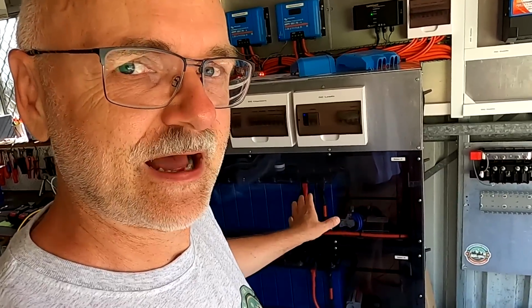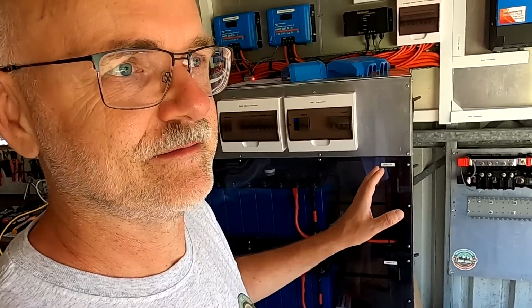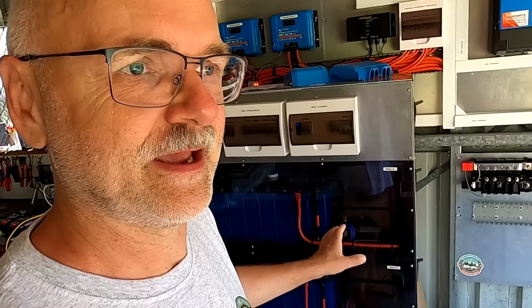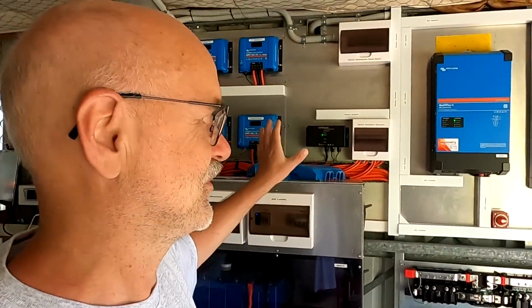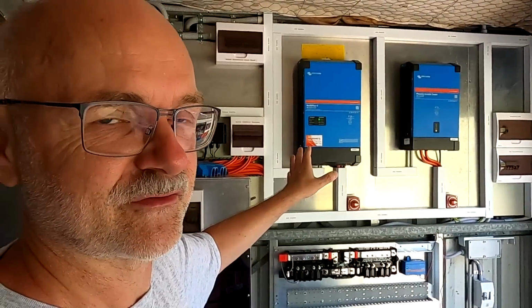And in this case, there's nothing to tell the solar charge controllers to slow down or stop charging. As long as they can measure the battery voltage, they keep pumping in the 250 amps as much as they can. So with such larger systems, I can see a certain need for having communication between the battery, solar charge controllers, and inverters as well.